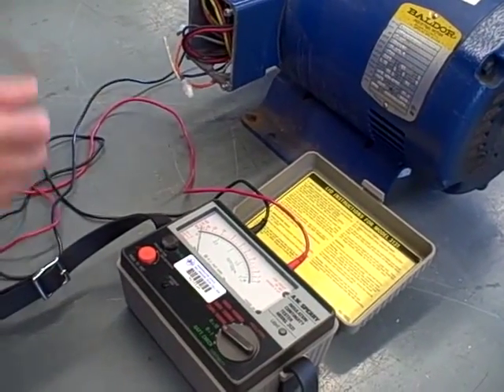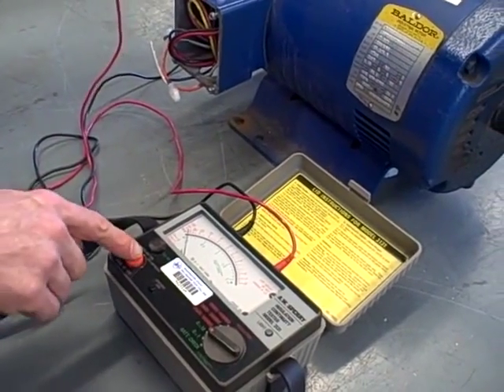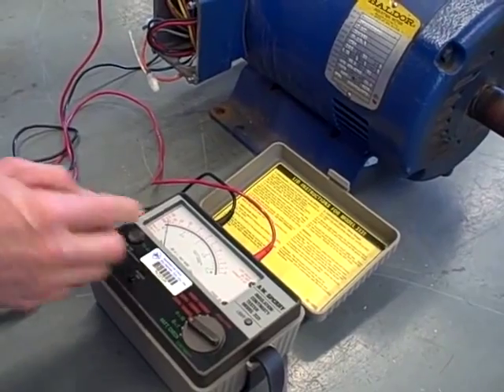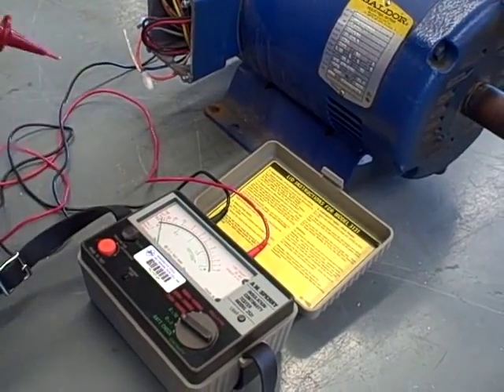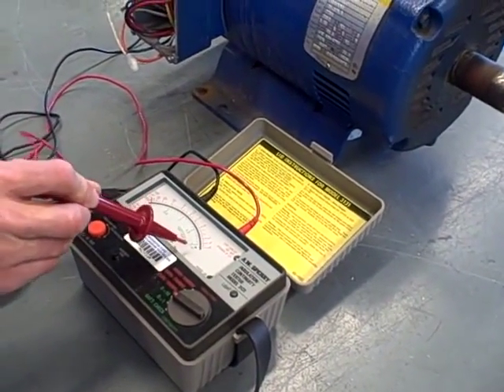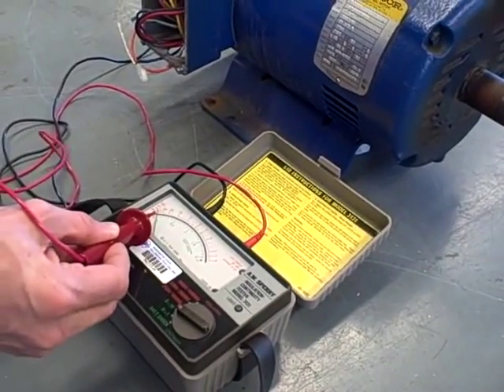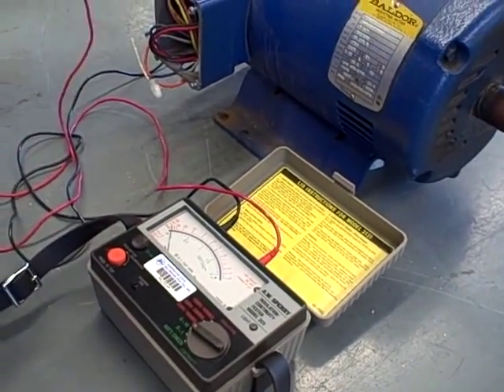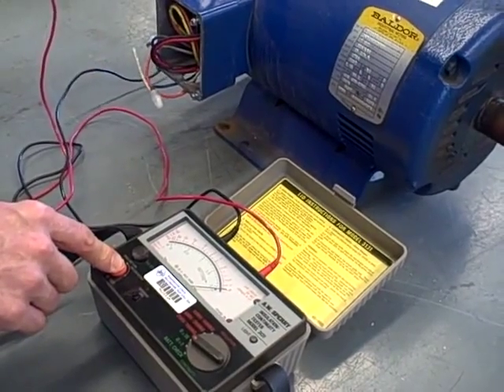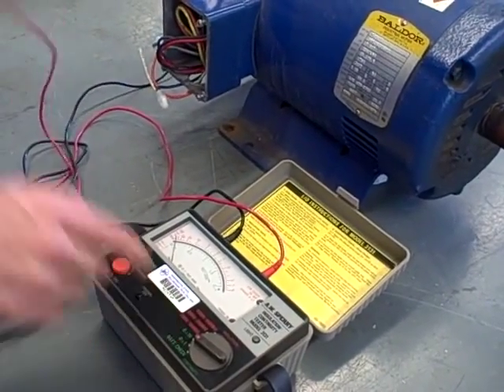Just to show you how this works, I can take this, touch to my ground clip, and you see right here, it stays on the left-hand side of the scale because on the green scale, right is infinite and left is 0. So a dead short would be the very left-hand side of the scale, and open would be the right-hand side of the scale on this low voltage setting.